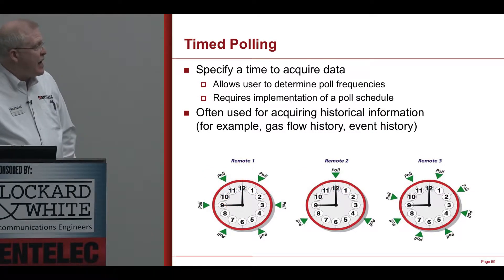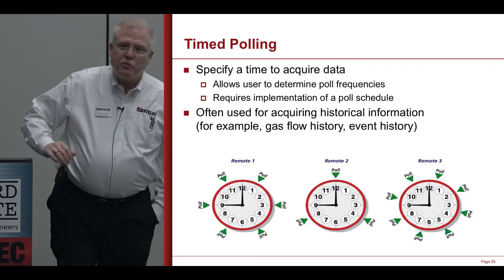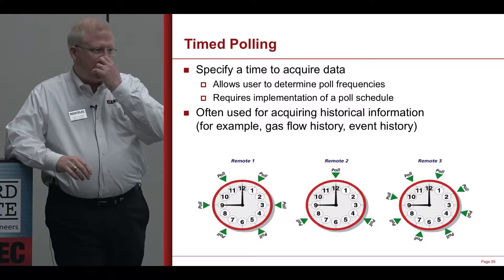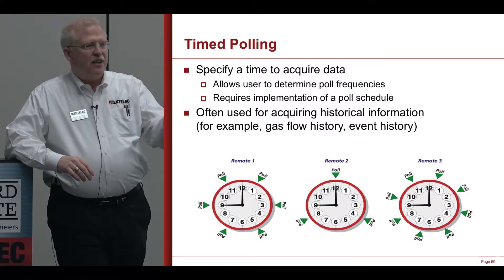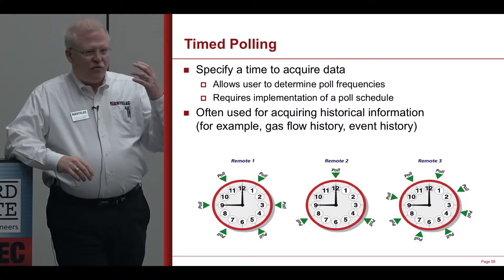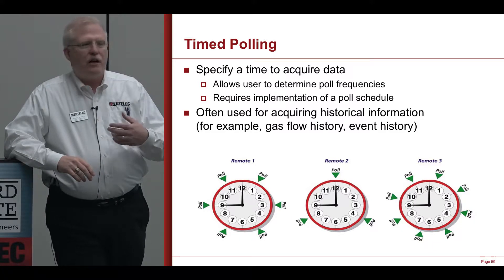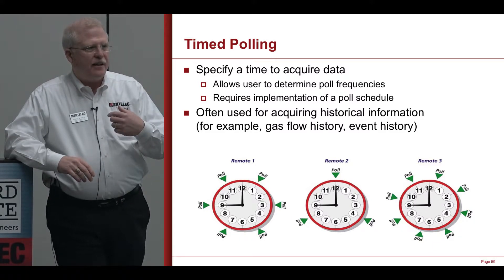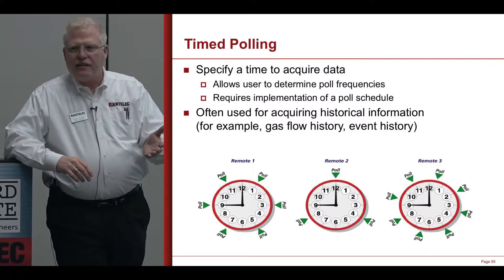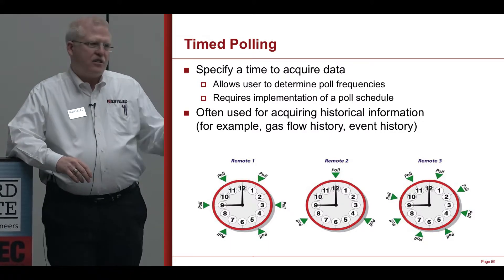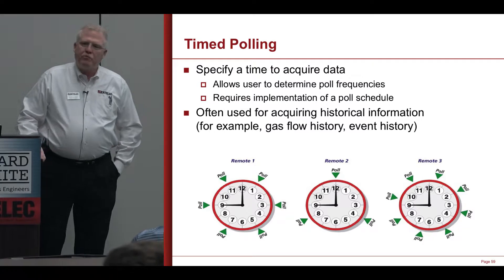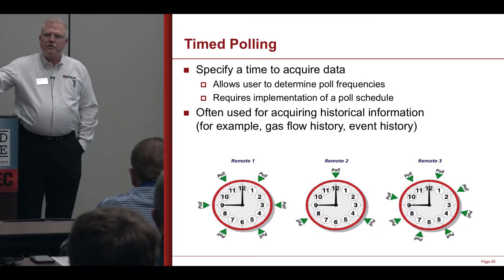There's also timed polling. We do that to collect measurement data — measurement data is accumulated in a flow computer every hour, so I don't need to hit it more than every hour. I'll schedule a poll to get the data at the end of the hour, and that's as frequently as I hit it. I use scheduled polling to do that, and that would be managed by the host.